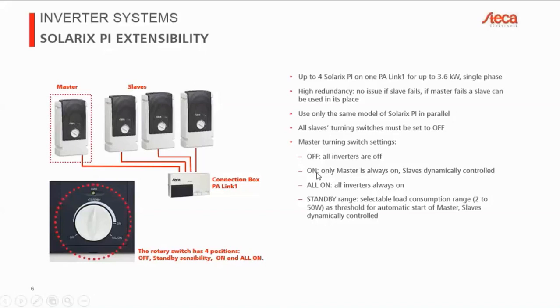The nice thing about the on switch, where only the master is running, is you only have 6 watts consumption here, and then 0.5 to 0.6 watts for the others. So let's say another 1.5 watts roughly, so 7.5. That's of course much lower, and especially for smaller systems, that can really reduce the amount of batteries and PV that you require.